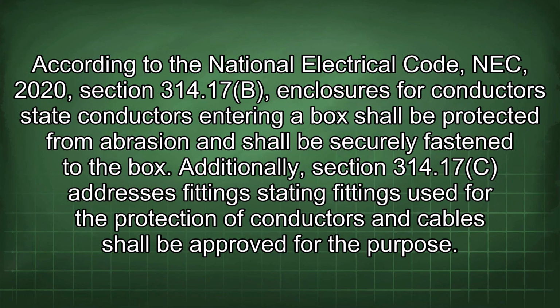According to the National Electrical Code, NEC 2020, Section 314.17(B), enclosures for conductors state conductors entering a box shall be protected from abrasion and shall be securely fastened to the box. Additionally, Section 314.17(C) addresses fittings, stating fittings used for the protection of conductors and cables shall be approved for the purpose.